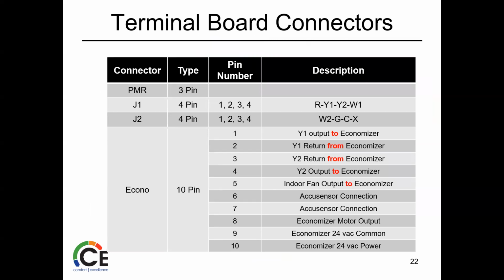So again, just some connections here on that economizer pin, that 10-pin wire that typically goes out to the economizer. If you don't have one, you've got a jumper plug in there and it's no big deal. If you have one, then of course it's wired in there. The biggest thing to remember is about that cooling. That cooling call comes from a thermostat, but it hits your economizer first before it gets anywhere. And we'll talk about that a little more in detail because that seems to confuse some folks.